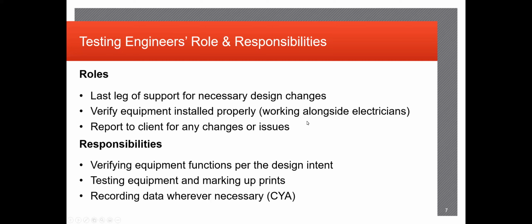Verifying the equipment installed properly, working alongside electricians as well. The electrician's primary purpose is realistically just to follow along the prints, identify what needs to be installed and or modified. And our job is to verify that not only they installed and modified stuff correctly, but to make sure and understand that it actually works per design intent.